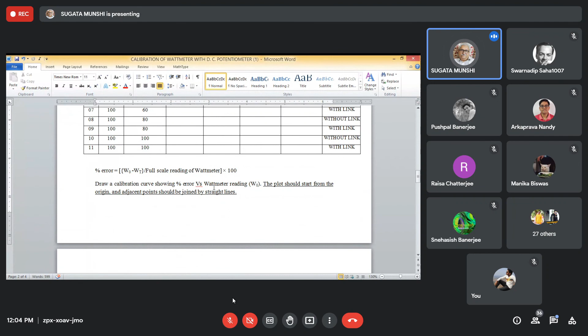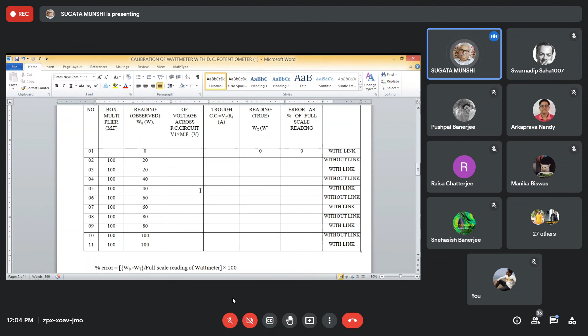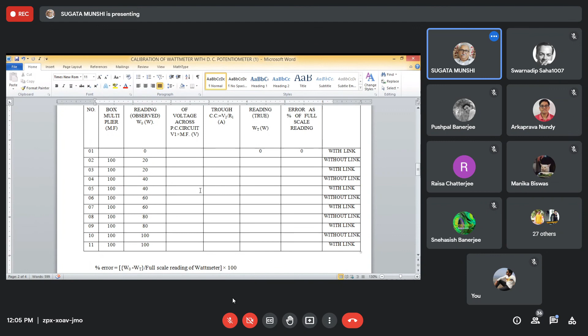It is because the variation of error across the scale of the instrument is random in nature. Say you take one complete set of measurements, you will find some error points. If you repeat it, there will be another set of error points. So you cannot say with certainty what the smooth nature of the curve will be. It is random in nature. So that's why you are joining the adjacent points by straight lines, indicating the trend of the error over such a small region. That is simply what you want to show when you join adjacent points using straight lines. Only the trend of the error. But you cannot say with certainty what the value will be. So that is the reason.